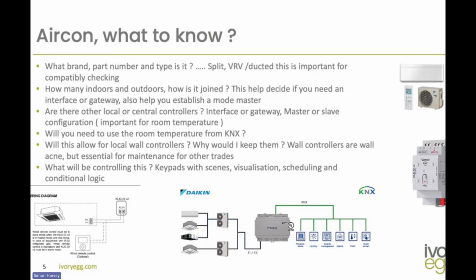Some installers don't want to go through KNX to do maintenance or adjustments to the aircon - they like to have wall controllers. What we suggest is putting that wall controller in the switchboard or a cupboard somewhere hidden, so we don't want it visible on the wall. This way we can take full control for the customer, while the local wall controller is hidden somewhere other trades can use for maintenance.